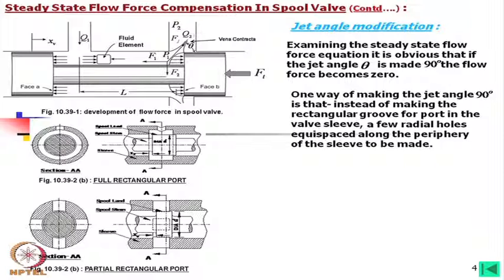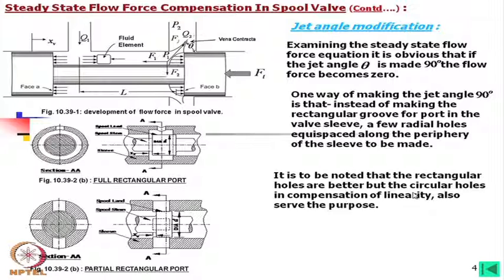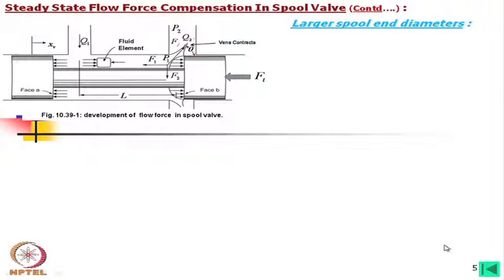It is seen that if we make such square holes, the flow jet angle may be very close to 90 degrees. Since cos(90°) = 0, there will be no component in the axial direction. It is noted that rectangular holes give better compensation, but circular holes also serve the purpose — they compensate the force, though with more nonlinearity.